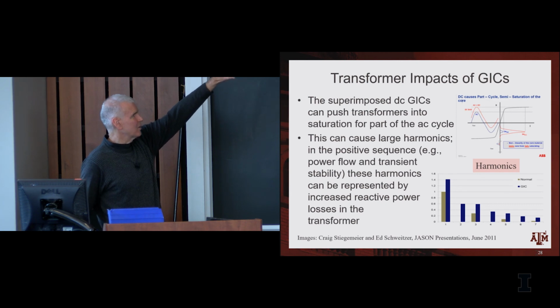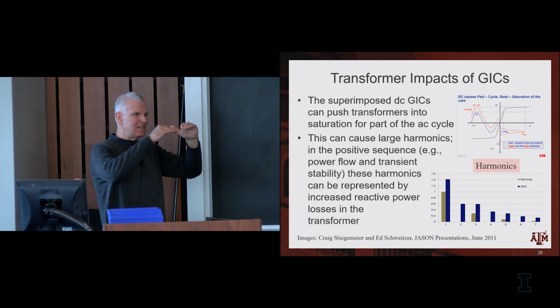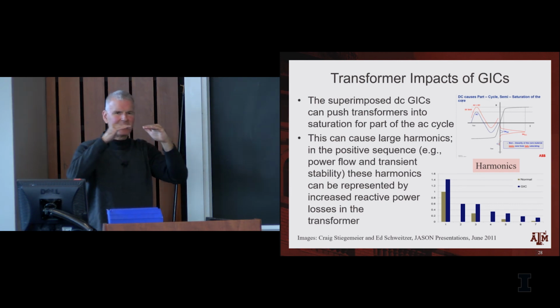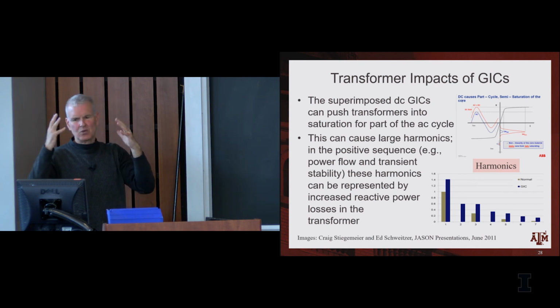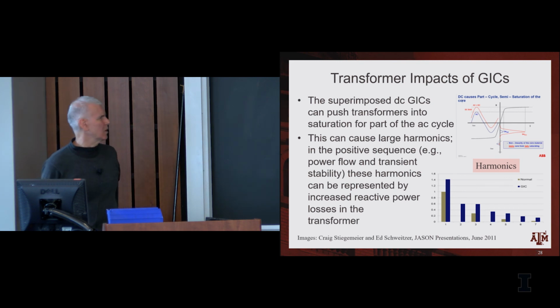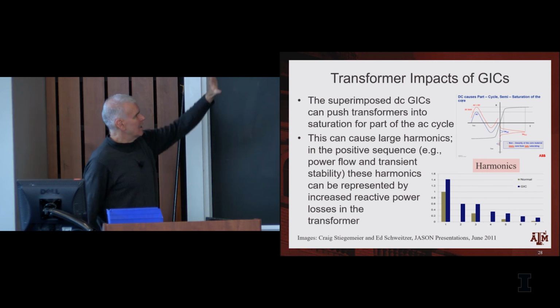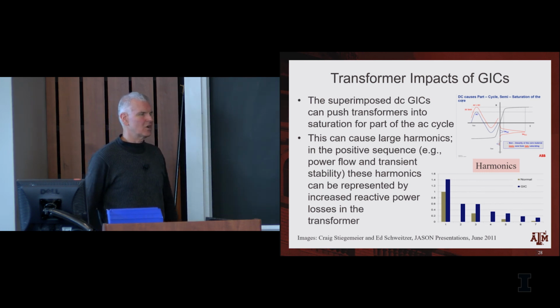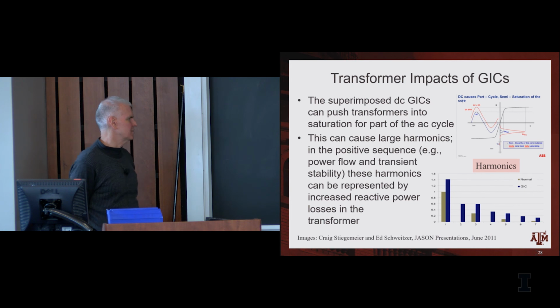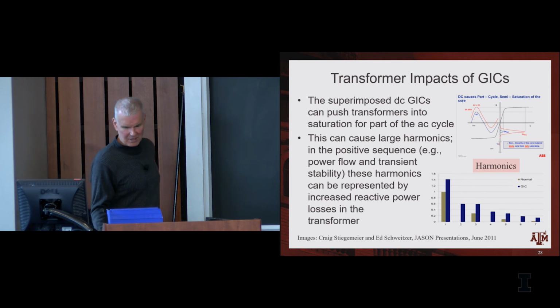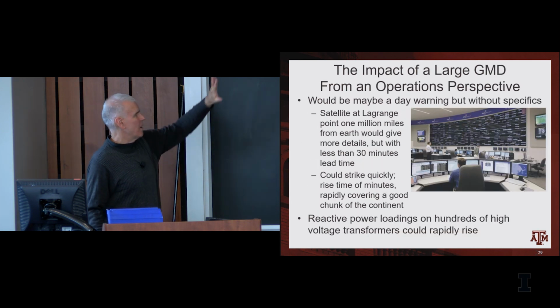One way they impact the grid is when you take an AC waveform and superimpose a DC waveform on it, you push it into nonlinearity. In a device using magnetic material, you actually cause saturation in the magnetic material. This introduces harmonics, and these harmonics can cause increased reactive power loss in your transformers.